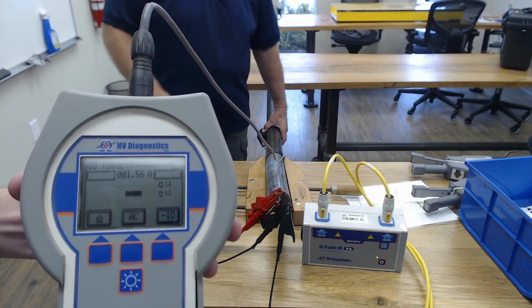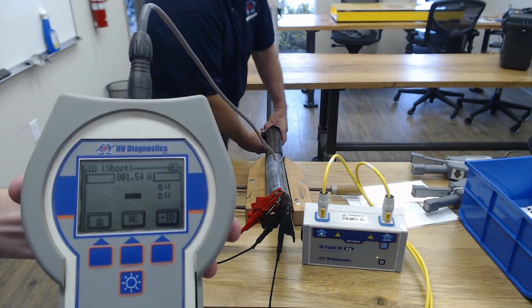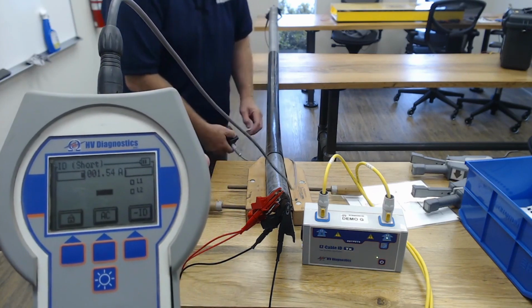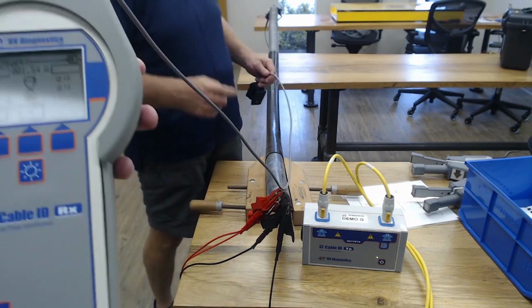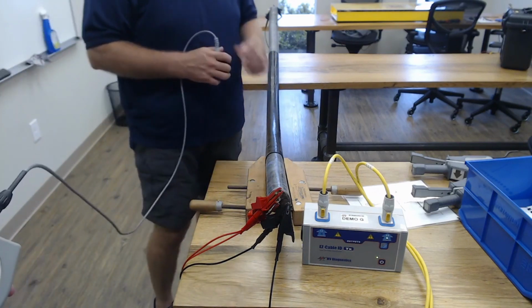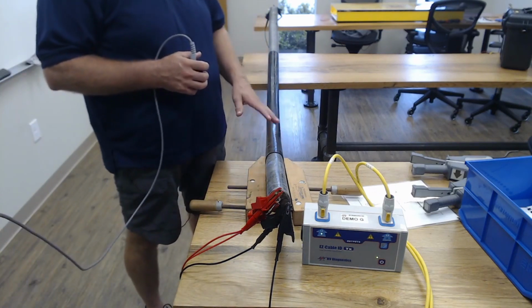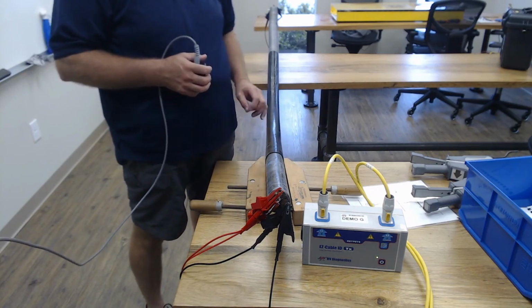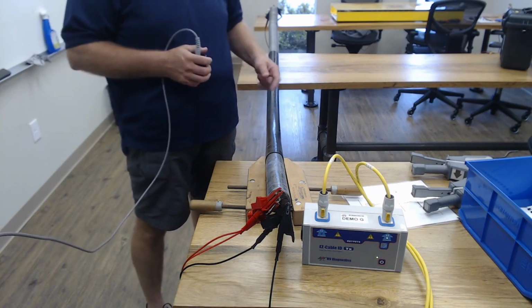And there we go. So on this particular cable, we've identified 3 bits of information. We've identified A phase, B phase, and the return. If you had to go in that same manhole or the same trench and look at any other cable, you would not have that information on any other cable.